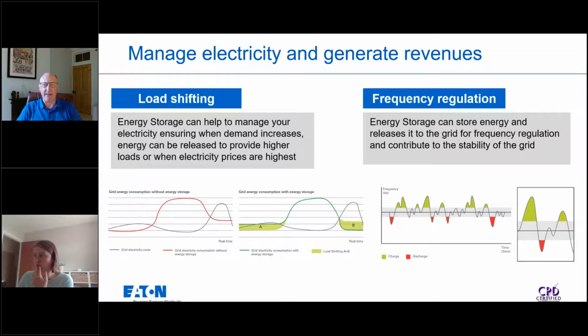Sometimes we see more complex tariffs, what we call pass-through tariff, where all of the different constituent elements of an energy bill are passed through to the consumer, and that then exposes that consumer to some of the other variable charges. And for example, that would be things like distribution use of system or DUOS charges, which have a green, amber and red zone, with the red zone having the highest charges, typically in that early evening period, and most usually 4 to 7 p.m, but it does vary a little bit geographically. And if you can reduce your consumption, then if you're exposed to that price differential, then you can have a bigger impact on your energy bill.